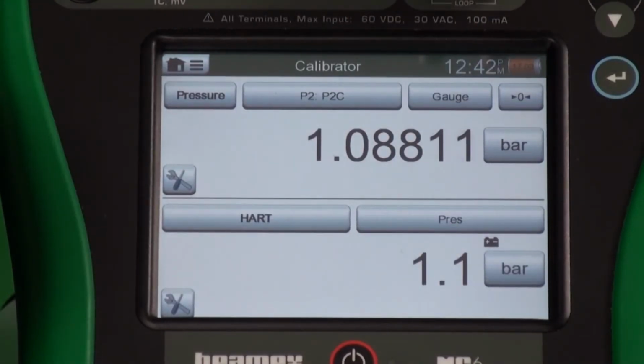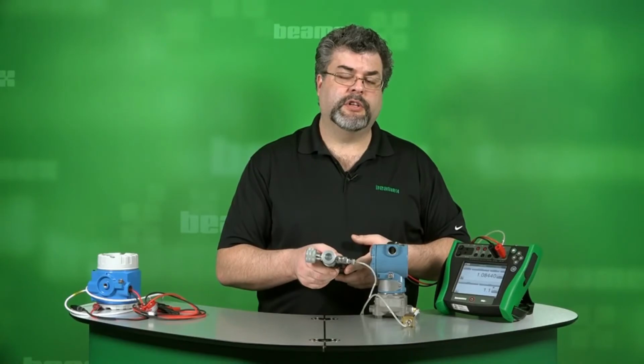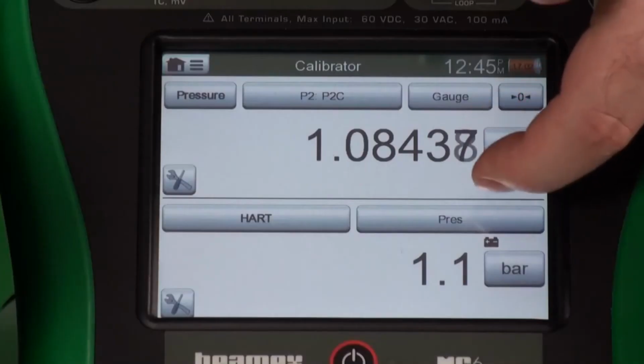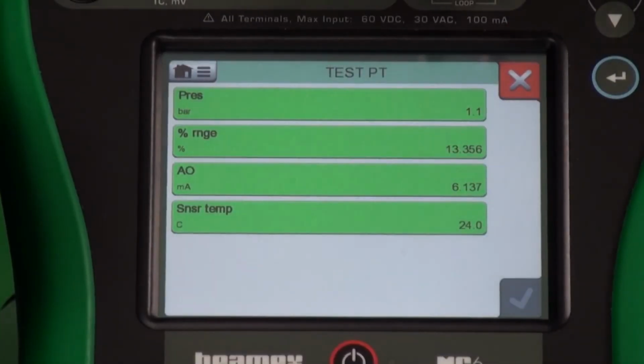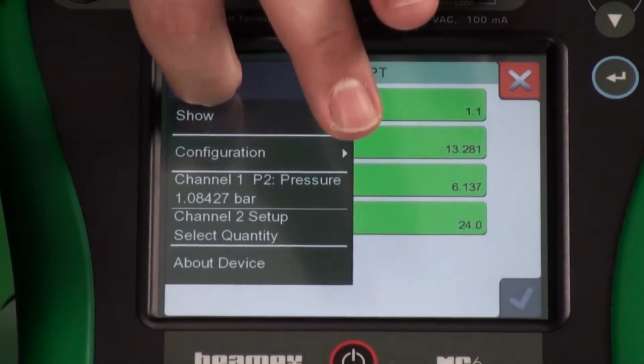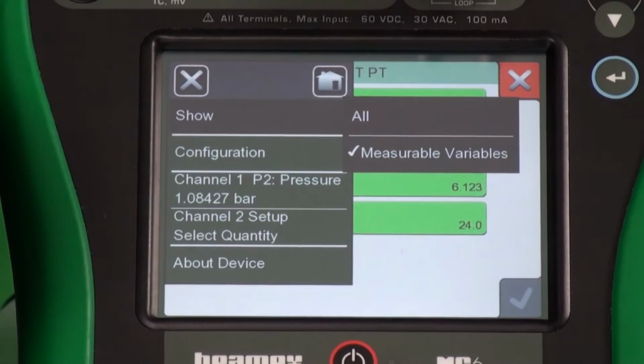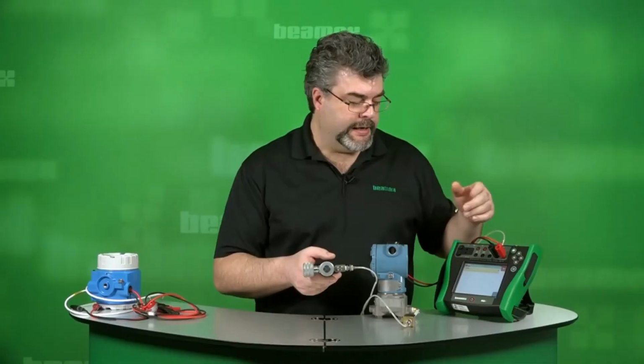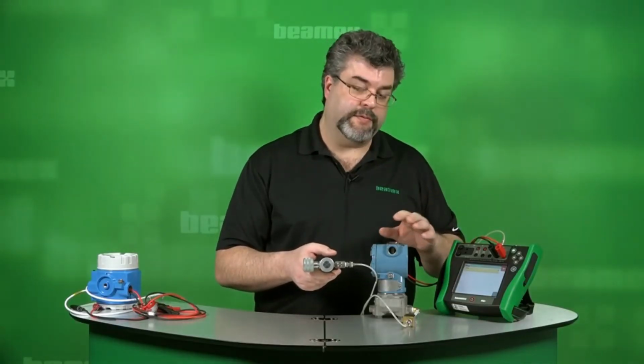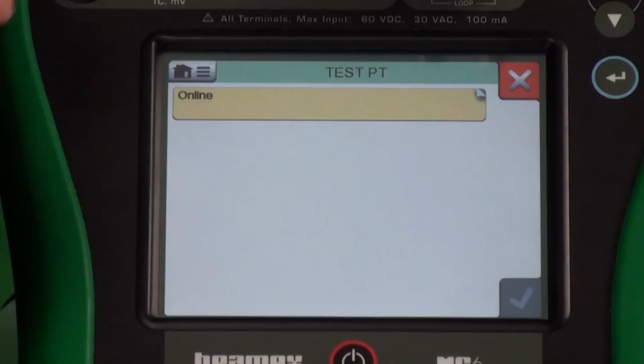So now we're measuring in the top screen and we're getting the actual output from the transmitter in the bottom window. Let's go back to communicator mode. Now from here we're still looking at the measurable variables. If we wanted to, we could go to show all so that we're looking at our standard structure again. But also while we're in here, we can save the configuration in here into its own file.